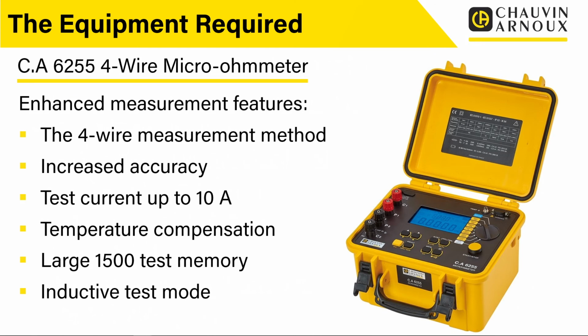It's got an actual external probe for temperature compensation. So that gives you the extra accuracy. It's also got a large test memory, so we can store up to 1500 tests in here. And it's actually got an inductive test mode. So when we were talking about being able to measure inductive loads, like motor windings and transformer windings, things like that, we said it can be problematic with reversing modes. This has actually got a specific mode on it designed specifically for testing those types of items. So if you're thinking of testing a lot of motors or generator windings, things like that, again, this is probably worth looking at because it's just got those extra functions on there and that increased accuracy. So still a very popular product, and again, just gives you a few extra features really above the 6240, but again, great product.